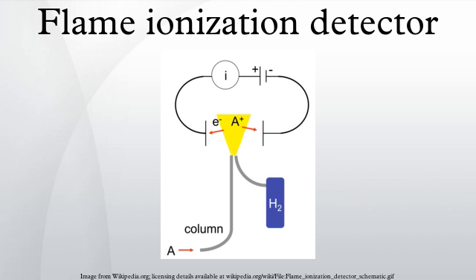All of the remaining compounds that contain carbon can be detected and quantified by integrating a polyarc reactor. The polyarc reactor converts all carbon-containing species to methane molecules right before reaching the detector through a two-step catalytic reaction, allowing things like CO, CO2, alcohols, acids, and other compounds that elicit a low signal from the detector to be quantified. A polyarc reactor also removes the need to use internal standards and calibration curves because every compound's response factor becomes unity.